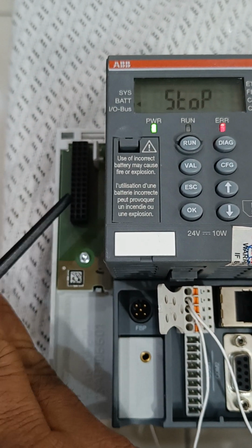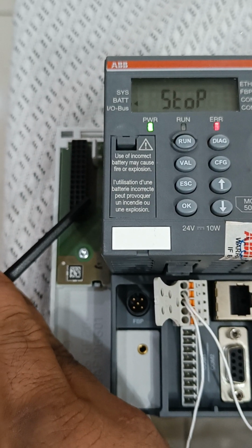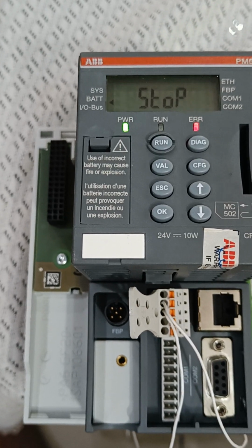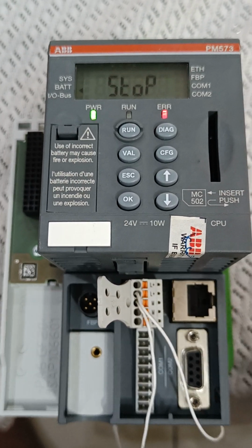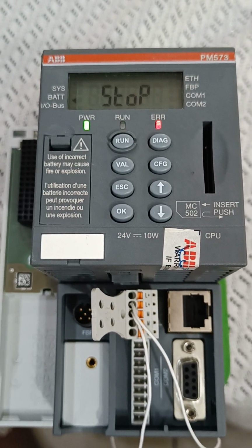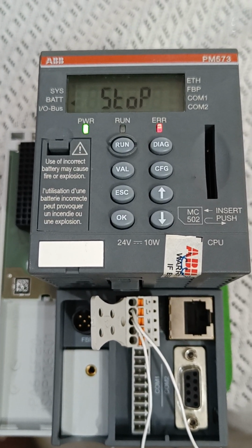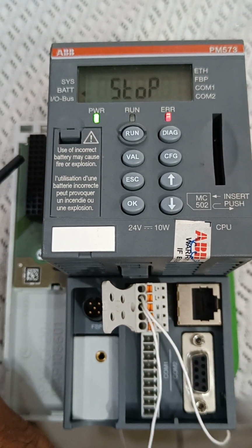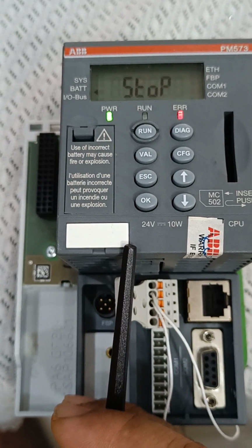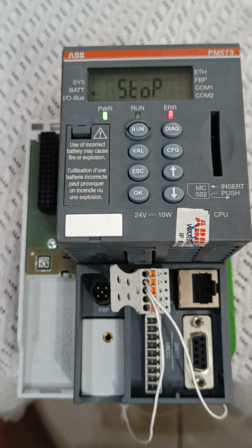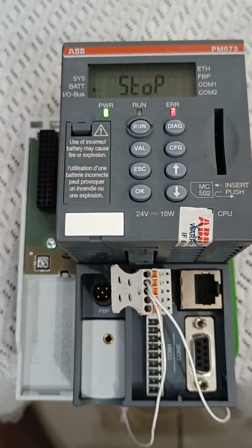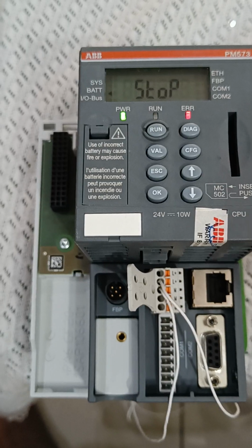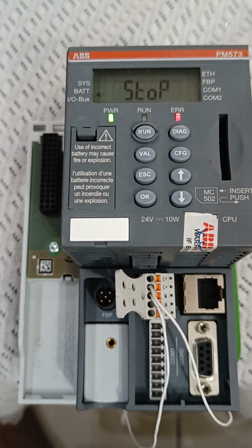So now you see this is the port available to install the communication module, and it depends upon the type of terminal base you are using. Here the TB511 ETH is the terminal base, and it supports one communication module. However, our PLC PM573 ETH can support a maximum of 4 communication modules. By installing a communication module, two more serial ports will be available for us.